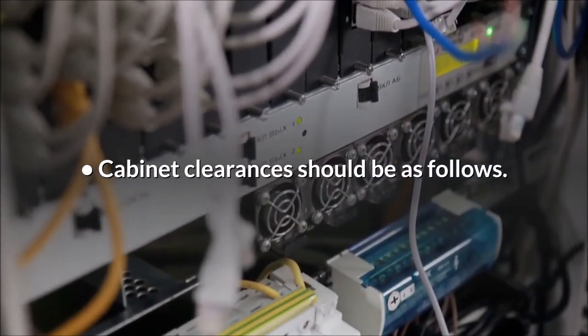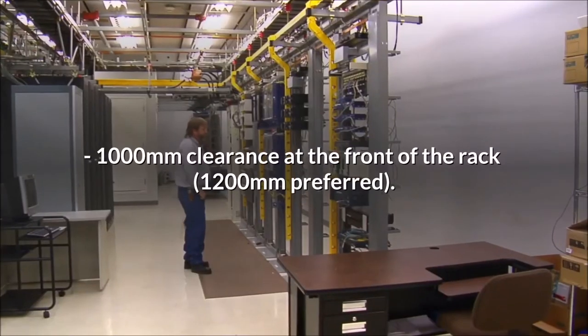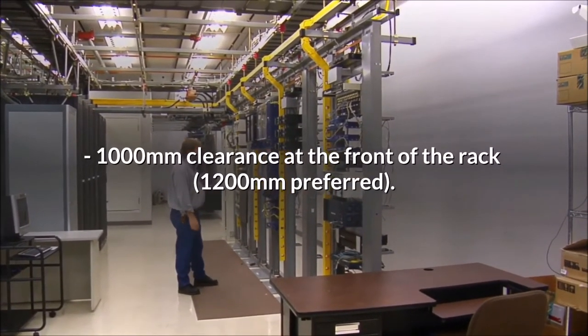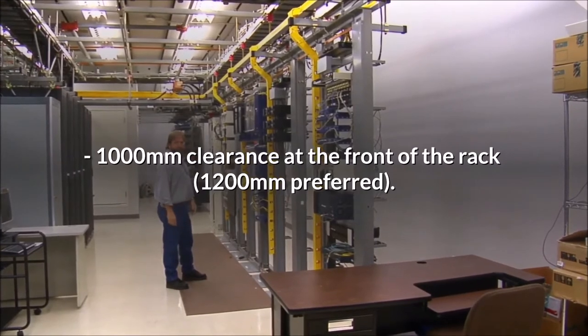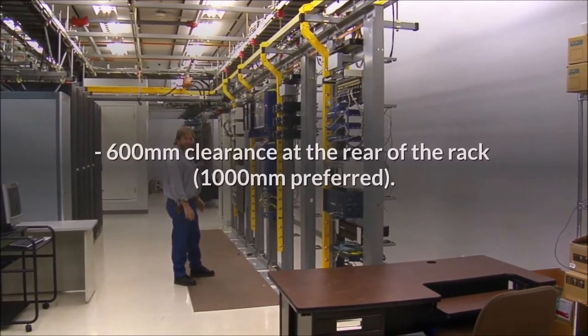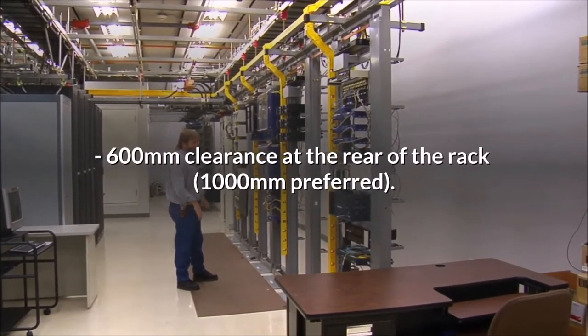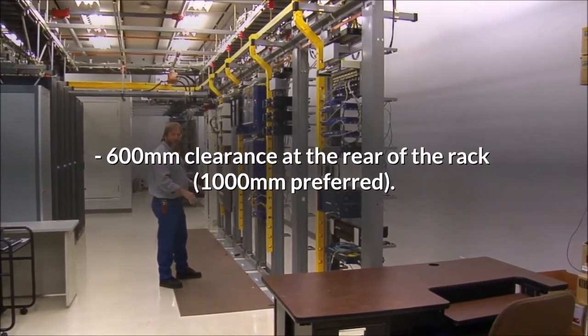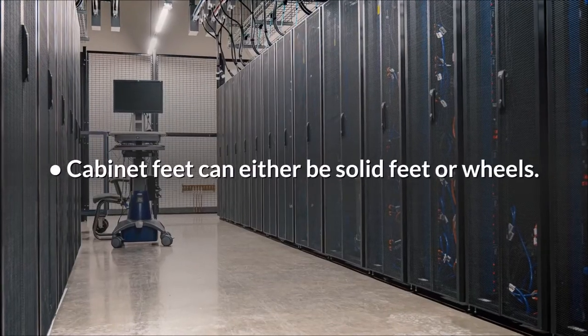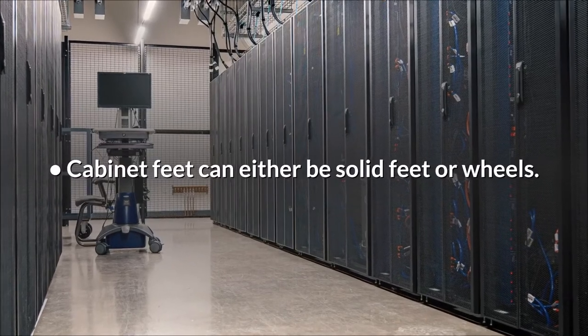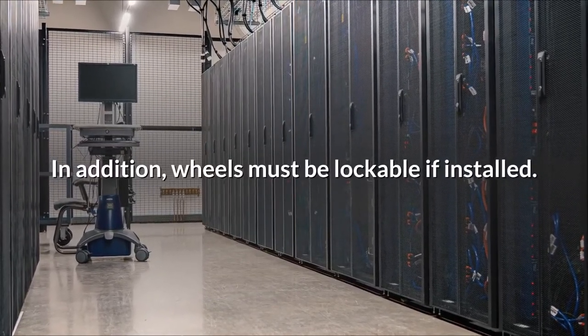Cabinet clearances should be as follows. 1,000 mm clearance at the front of the rack, 1,200 mm preferred. 600 mm clearance at the rear of the rack, 1,000 mm preferred. Cabinet feet can either be solid feet or wheels. In addition, wheels must be lockable if installed.